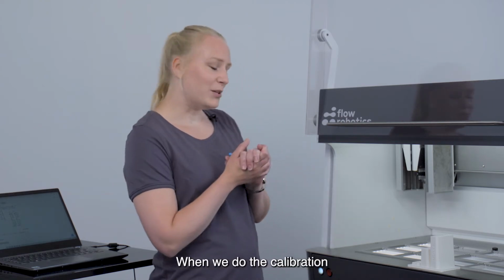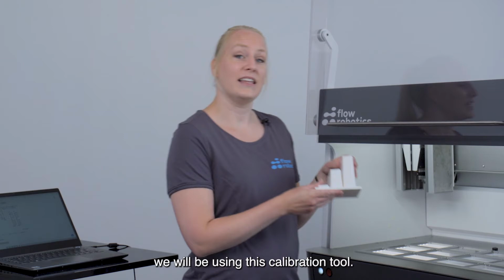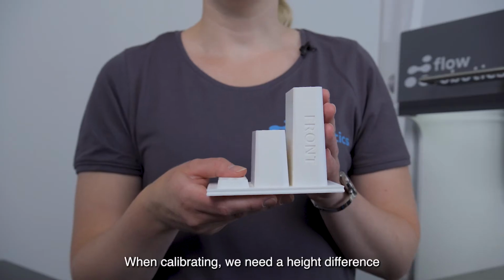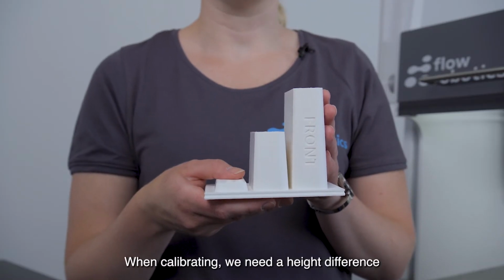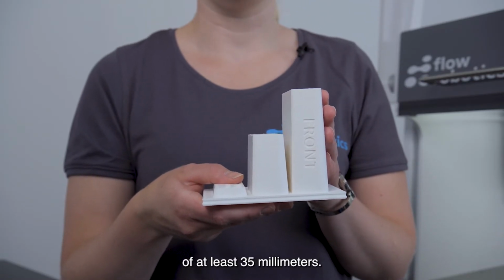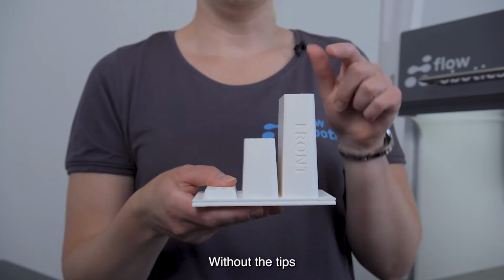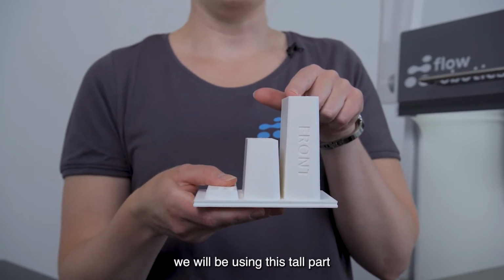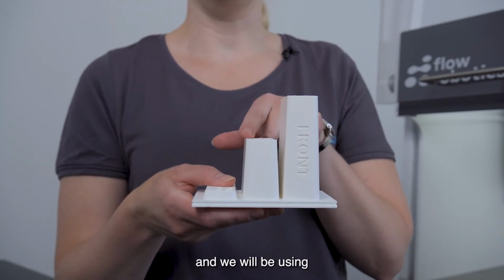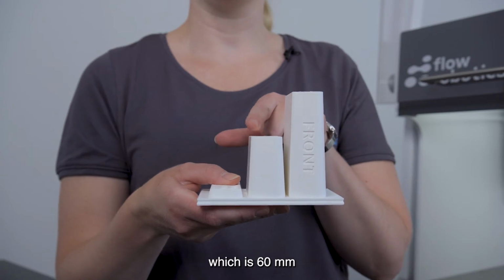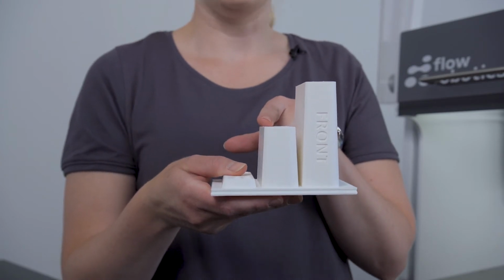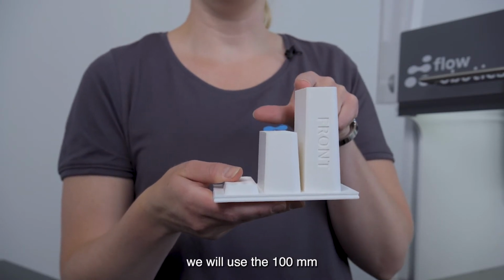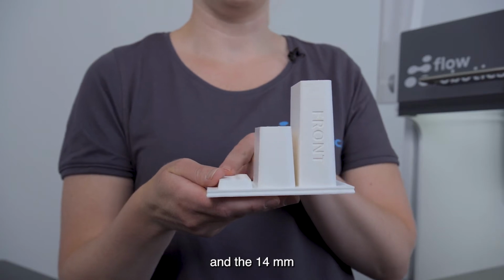So when we do the calibration, we will be using this calibration tool. When calibrating, we need a height difference of at least 35 millimeters. So without the tips, we will be using this tall part here, 100 millimeter, and we will be using this part in the middle here, which is 60 millimeter. For without tips, we will use the 100 and the 14 millimeters.